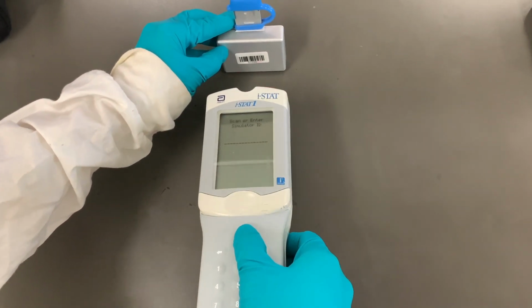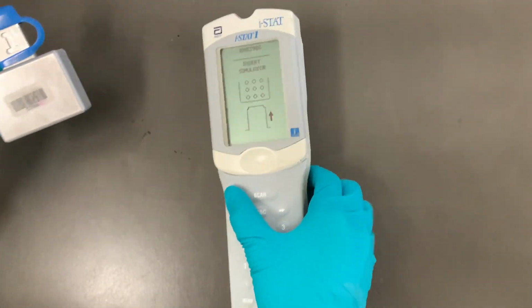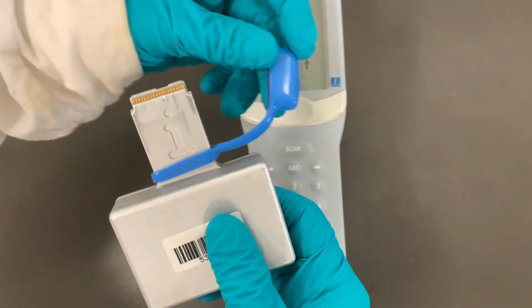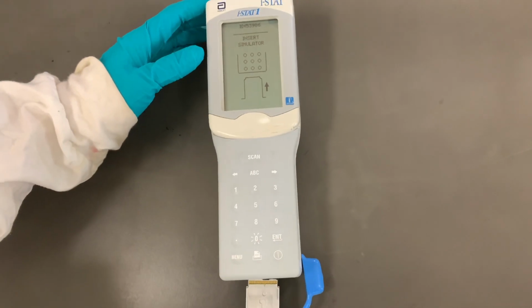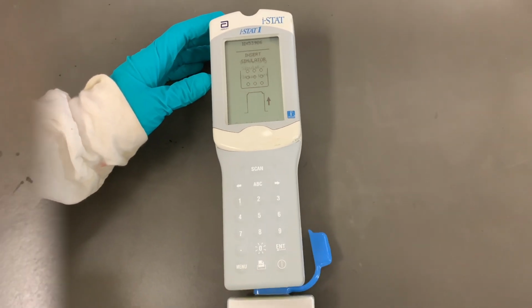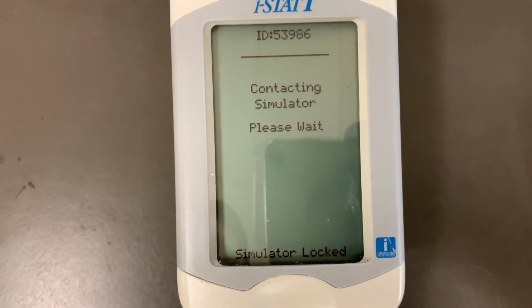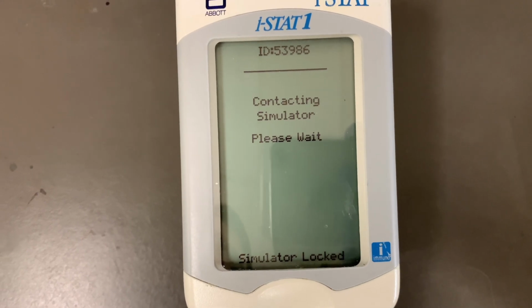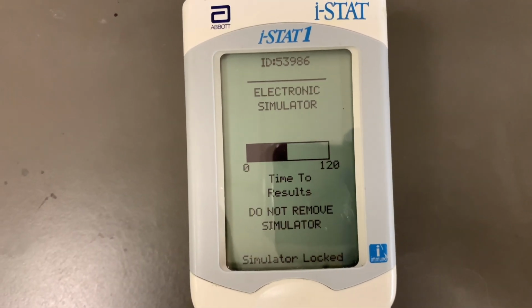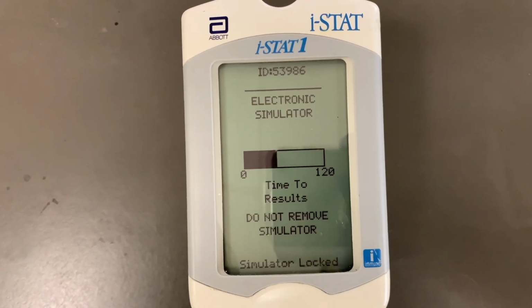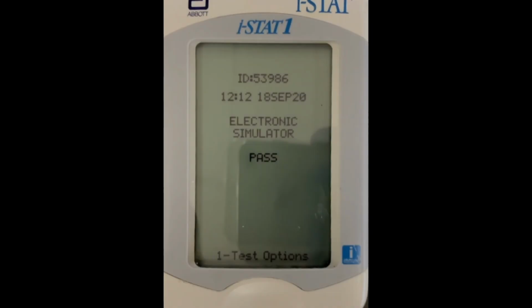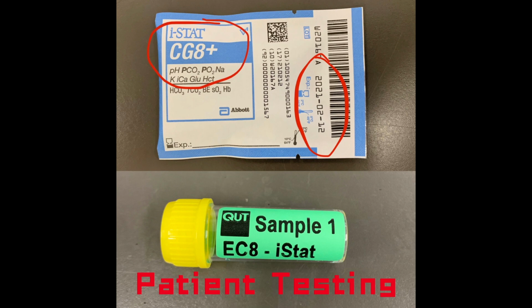As you can see, I'm having a bit of trouble scanning it. Now take the blue lid off and then you can insert the simulator. It will approximately take 2 minutes for calibration. During this calibration, you can make sure all the equipment is ready to use before patient testing. If the calibration is successful, it will show pass on the screen. And now you can perform patient testing.